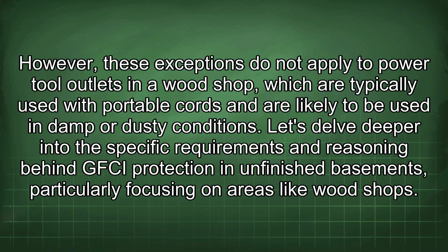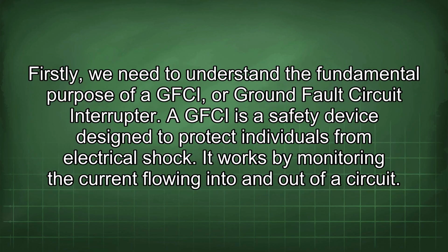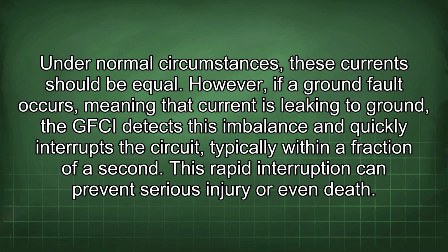Let's delve deeper into the specific requirements and reasoning behind GFCI protection in unfinished basements, particularly focusing on areas like wood shops. Firstly, we need to understand the fundamental purpose of a GFCI, or ground fault circuit interrupter. A GFCI is a safety device designed to protect individuals from electrical shock. It works by monitoring the current flowing into and out of a circuit. Under normal circumstances, these currents should be equal. However, if a ground fault occurs, meaning that current is leaking to ground, a GFCI detects this imbalance and quickly interrupts the circuit, typically within a fraction of a second. This rapid interruption can prevent serious injury or even death.